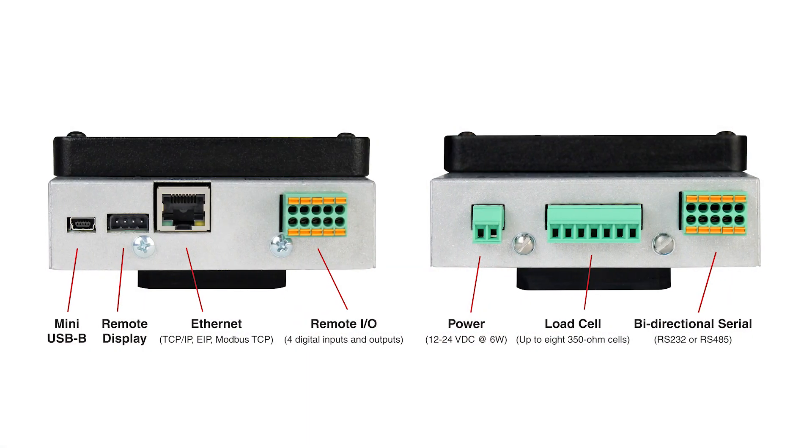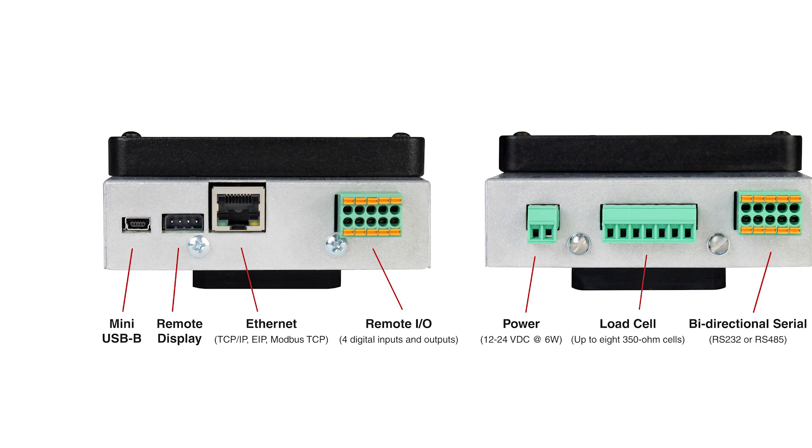Let's talk about some of the features with the 201. It can power up to eight load cells of 350 ohms. This is not designed as a truck scale application. The neat thing about the 201 is all the communication features are already built into it. Another nice feature about the 201 is the mounting. So most 201's are applied in a UL listed cabinet. Besides this being NTEP certified, it also is UL listed.